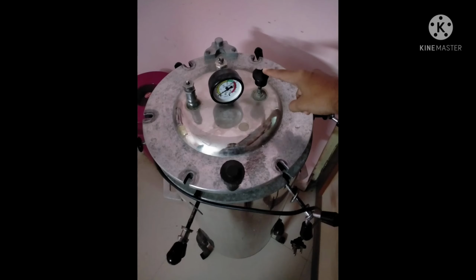Put whatever indicator you have available, like the class B or other indicator. After that, start the autoclave by switching on the power and the steam starts to come out. The basic problem is that if we lock the autoclave at this stage, the air gets trapped inside, and this air prevents the steam from reaching the temperature of 121 degrees centigrade, which is required for killing almost all the spores. So we have to get rid of this trapped air. For this we have to release the pressure releasing valve for at least 10 minutes so that all the trapped air gets replaced by steam. Now we can run the autoclave.